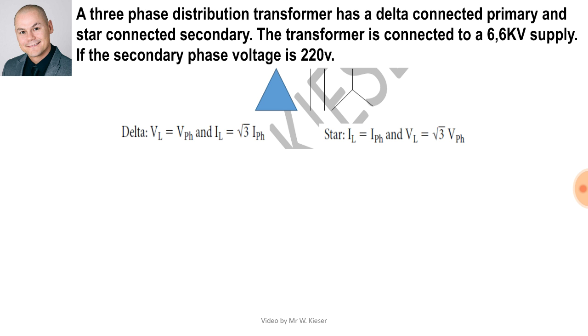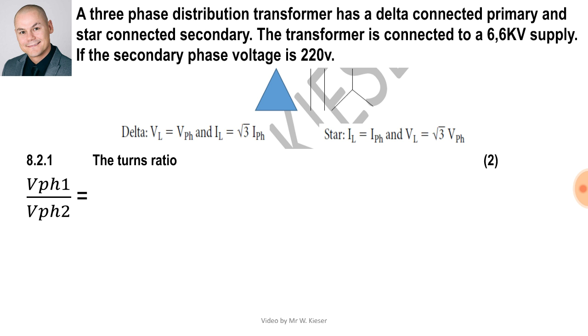Next question: a three-phase distribution transformer has a delta connected primary and a star connected secondary. The transformer is connected to a 6.6 kilovolt supply. If the secondary phase voltage is 220 volts, we're going to calculate the turns ratio. When working with the turns ratio, remember we use phase values, so it's V phase one over V phase two. Since primary is delta connected, VL1 equals V phase one, giving 6600 volts. V phase two is 220 volts. Therefore 220 goes into itself once and into 6600 thirty times, giving a turns ratio of 30 to 1.